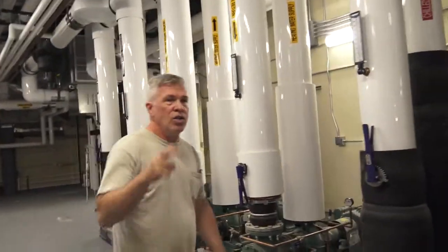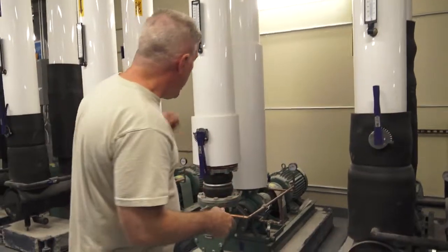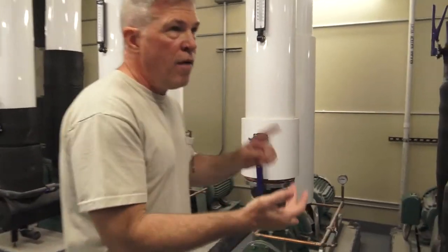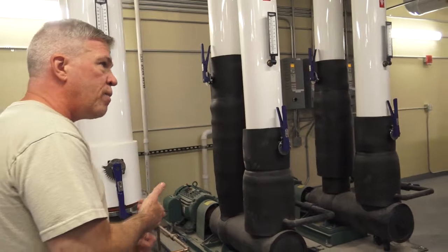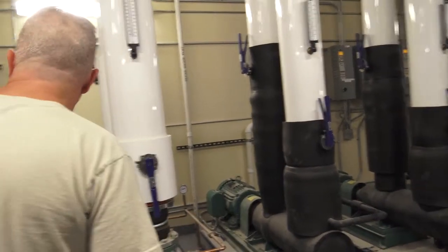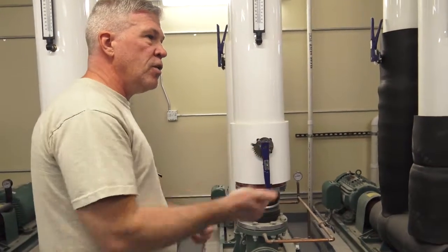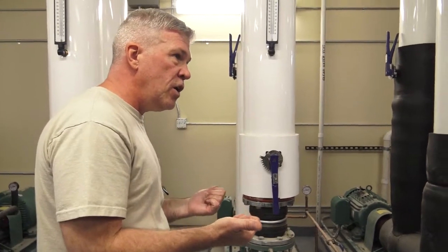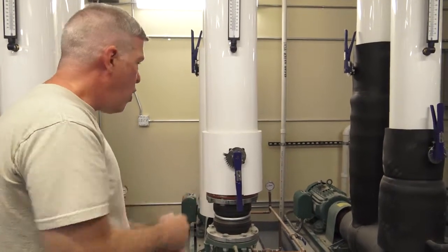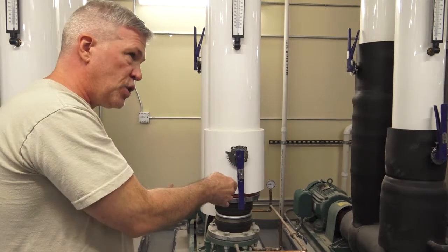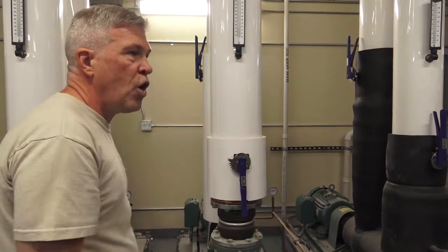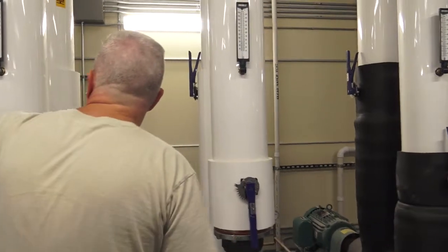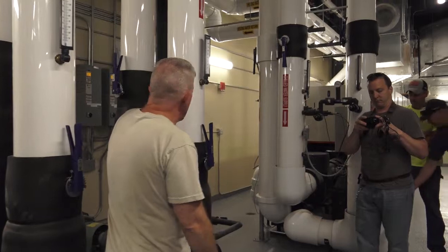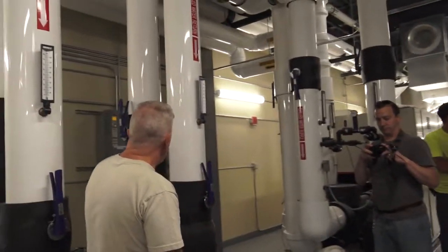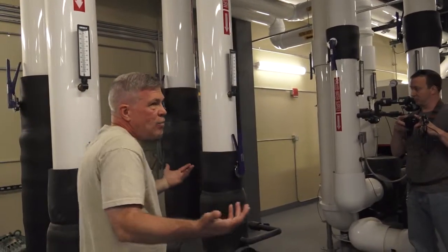So for your hot water, chill water system, it's kind of like Sparta where you have geo pumps, but here you also have hot water pumps and chill water pumps. There's two of each pump style, so they're lead lag and redundant on each other. Once a week they'll rotate, or on a failure of the lead pump, the lag pump will turn on and run. So kind of like what you normally see. Drives, the two down there are the geos, and they're kind of listed on, but you have hot water pumps and chill water pumps. So same drives kind of situation.